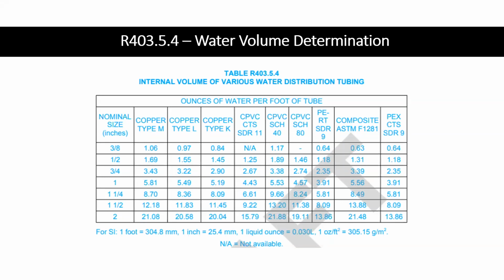So looking at the nominal size of piping, if you have a 1/2 inch pipe, then you look to the right across the top and you see what it is made of. So if you have PEX piping all the way at the end, you have a 1/2 inch pipe of PEX piping, you have 1.18 of that volume. That's ounces of water per foot in the tube. So you have to calculate some of that. It'll get a little confusing on the first couple of times you do it. Of course, more than likely, most of it's going to be always that same size, that 1/2 inch or maybe 3/4, possibly 1 inch. You won't really get too many that are larger in residential homes.